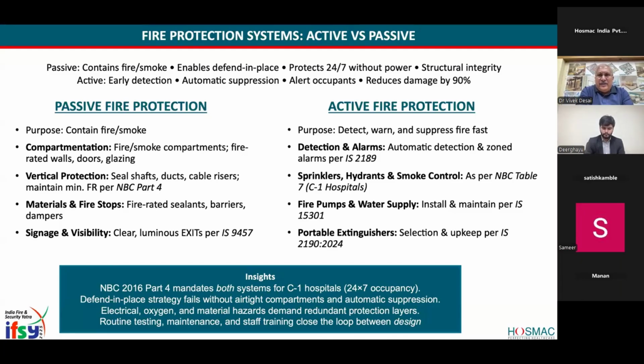In terms of active measures, it is simple: detect, warn, and suppress. It will detect, and it will automatically operate the sprinkler systems, provided they are maintained. That is something I keep harping on. Detection and alarms, sprinklers, hydrants, fire pumps and water supply, you should install and maintain. I am again underlining the word maintain. We don't. There was a recent fire somewhere in Mumbai about 3 days back, and the fire hose didn't work. It was in a tall tower.